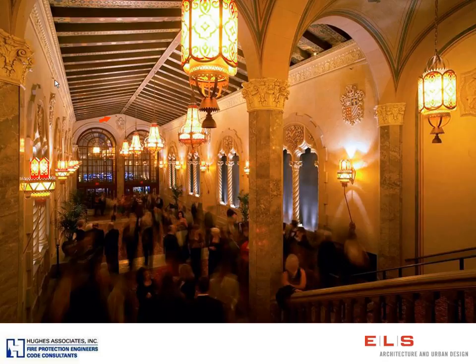So what Kurt was describing is that when we install a sprinkler system, the sprinklers have to be able to collect heat, because I was showing earlier how all of your smoke and hot gases are going to bank here up at the ceiling. And these sprinklers that we installed are technically, by the code, meaning the fire sprinkler standard, NFPA 13, too far down from the ceiling. So there's a potential that by the time the heat banks back down, there could be a little bit of a delayed reaction. And that was why we installed this projected beam detector, to mitigate the fact that these sprinklers were just a little bit lower from the ceiling than what the code allowed. And so this was actually a design, an alternative method that we ended up negotiating with the authority having jurisdiction, the San Jose Fire Department, in order to retain the character-defining feature of the space, the ceiling here.